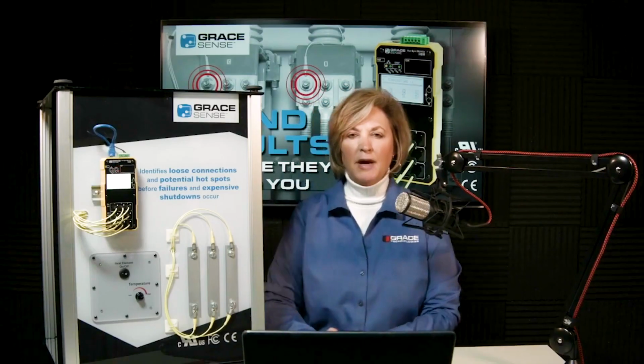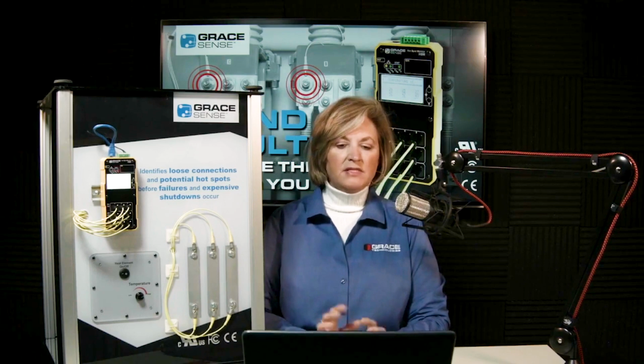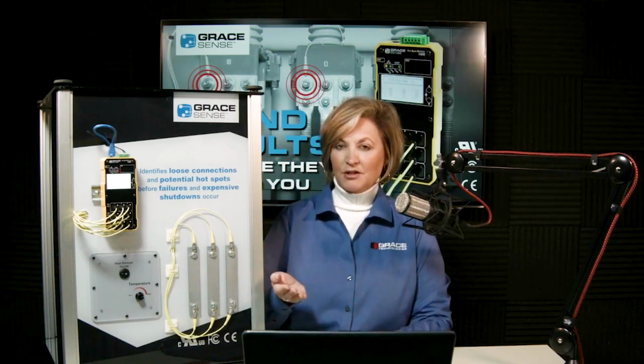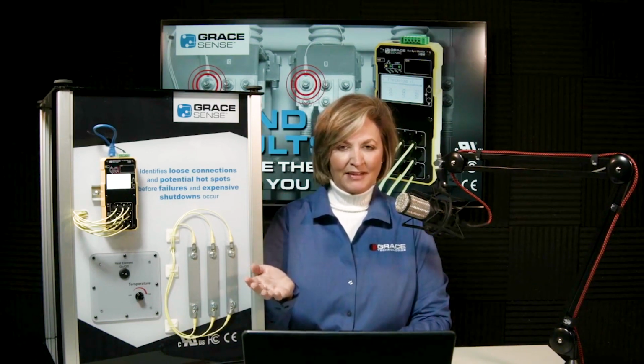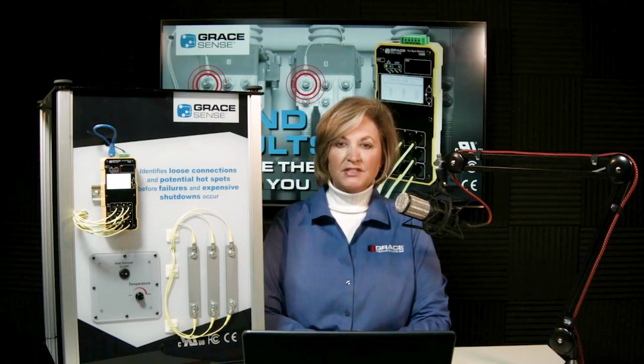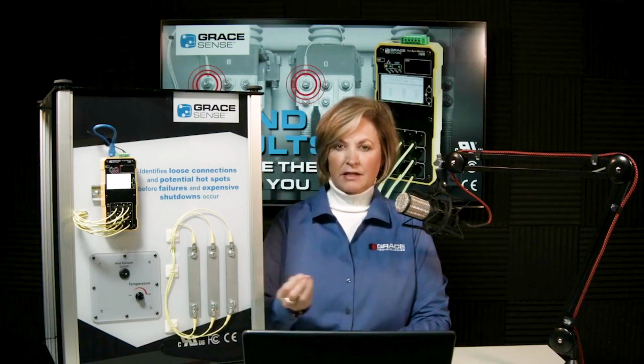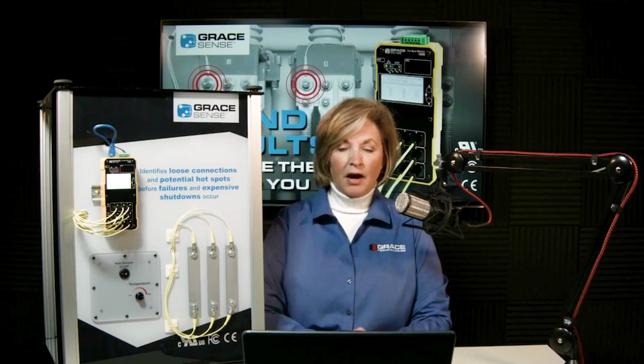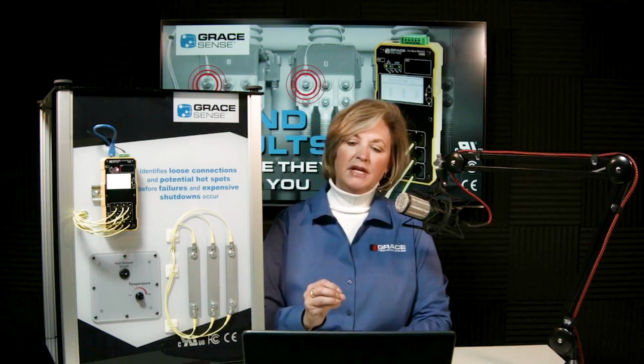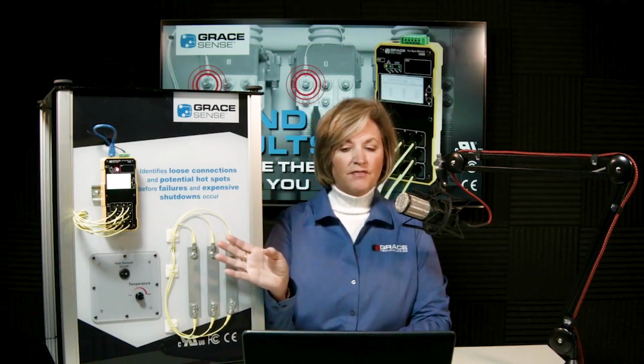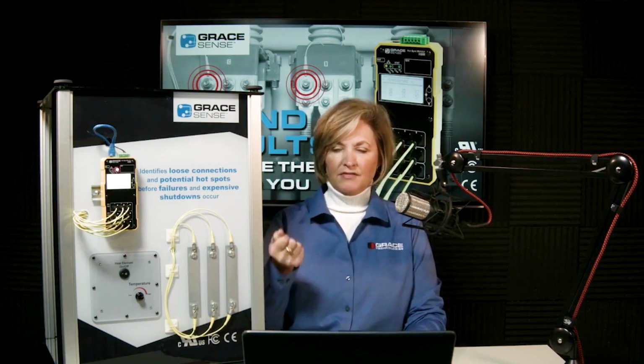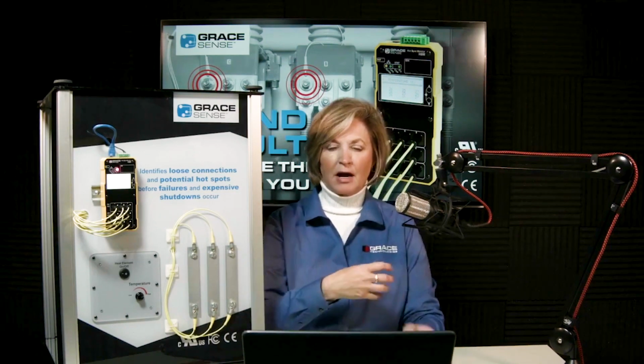I also want to talk to you about the concept called dark fiber. This is a situation where a shutdown happens, either on schedule or not on schedule, and you have the opportunity to install the fiber because the equipment is de-energized. We highly encourage taking this opportunity to install the fiber, get it routed up into your low voltage compartment, so that when you do have to energize, the system is ready to go, and we don't have to worry about taking the time to install the electronics at that time.